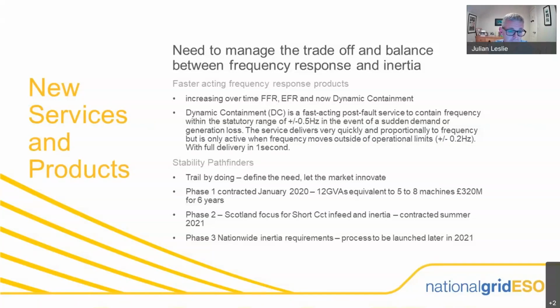We contracted in January 2020, just 2 years ago, and already most of the machines we contracted for are on the network. These machines in phase one were either a pump storage plant that is just spinning its turbines in air or in water and providing that inertia, but it's a dedicated unit for inertia and short circuit infeed. We have a gas-fired power station that has converted itself to be a rotating synchronized motor, effectively, again providing inertia and short circuit infeed, which is really great, repurposing an existing asset. It's a pretty low cost to do that.